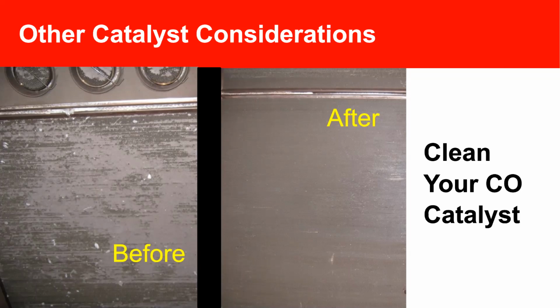So that's why we keep this upstream of the AIG. With it being in that location, if the CO catalyst becomes plugged, you can create bulk flow maldistribution to the AIG and SCR system, which can create a headache when you're trying to balance that system and maximize its performance. You create pockets of high flow and low flow, and it just makes everything more difficult downstream. So it's important to keep that clean. This is also true for units that don't have a CO catalyst. Any equipment that's upstream matters. Just keep in mind that the bulk flow to the AIG and SCR system does make a difference when you're trying to maximize performance.